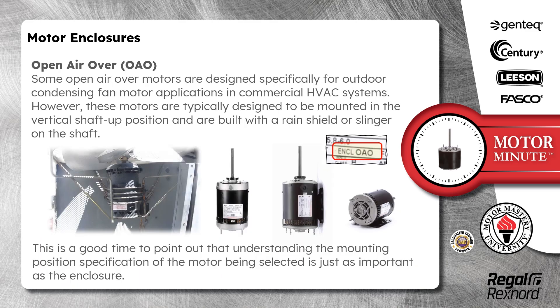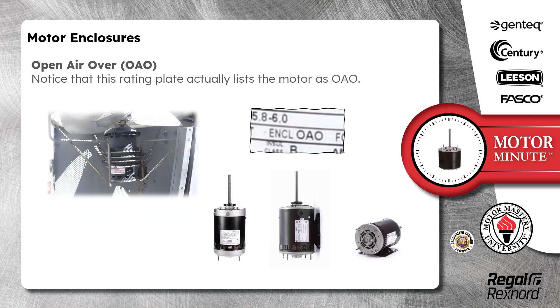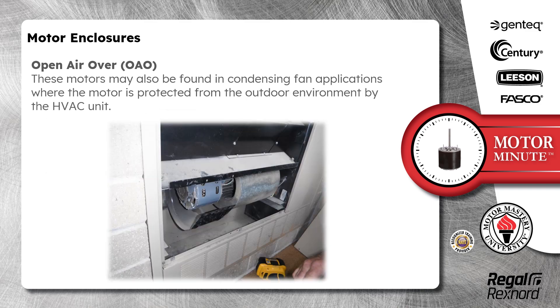Some open air over motors are designed specifically for outdoor condensing fan motor applications in commercial HVAC systems. However, these motors are typically designed to be mounted in the vertical shaft up position and are built with a rain shield or slinger on the shaft. This is a good time to point out that understanding the mounting position specification of the motor being selected is just as important as the enclosure. Notice that this rating plate actually lists the motor as OAO. Open air over motors may also be found in condensing fan applications where the motor is protected from the outdoor environment by the HVAC unit.